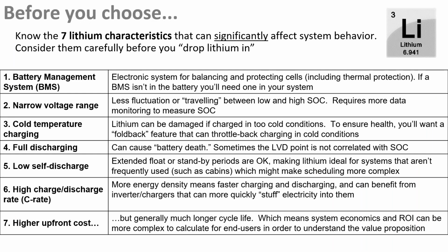So what we've boiled it down to here is 7 lithium characteristics that you should be aware of if you are transitioning from lead acid as a drop-in replacement, as Nate was talking about earlier. One is the existence of a battery management system. So that's very important, obviously, for lithium because, as Nate mentioned, the cells can become unbalanced, and that imbalance, although it's not as problematic in lead acid batteries, can become problematic in lithium batteries.